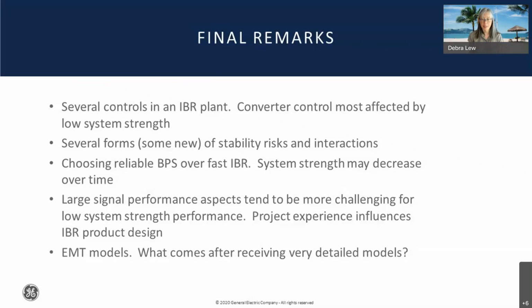That's a great question. System strength can be seen in two ways: one related to voltage magnitude and reactive power, and one regarding angle, frequency, and active power. On the voltage magnitude and reactive power side, yes - some grid following IBRs do that, since they have terminal voltage controls with relatively fast response times, like 100 milliseconds or so. So within that timeframe of terminal voltage regulation, you are creating a kind of virtual system strength, which may help other IBRs connected nearby. If you need to create virtual system strength on faster timeframes, you may need to look at grid forming aspects.